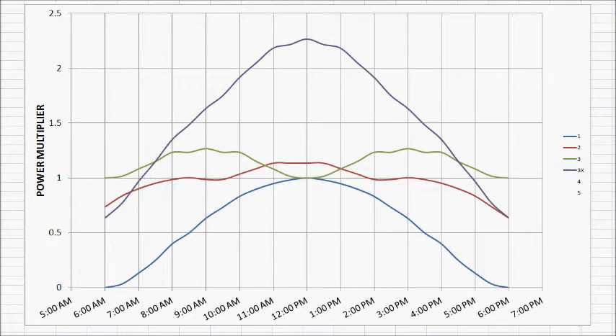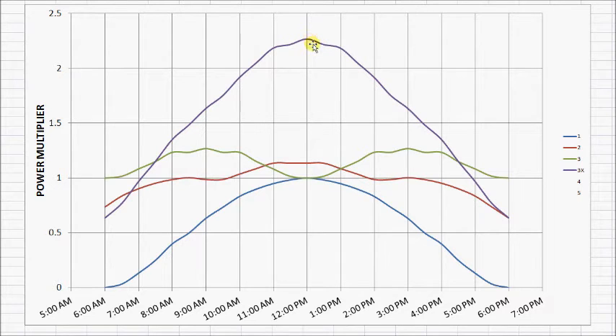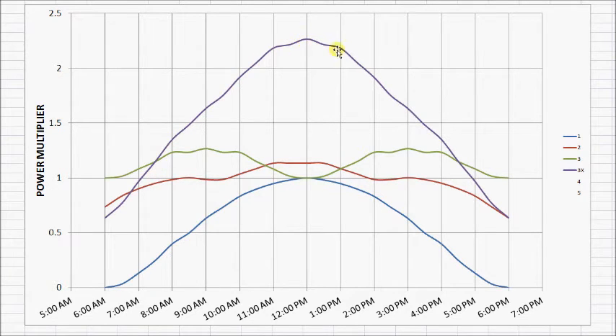If we look at the other configuration of three panels — one to the southeast, one to the south, and one to the southwest — clearly all three of them are contributing very well. The one facing due south is putting in its full amount, and the ones facing southeast and southwest are doing about two-thirds of their production right at noon. So you'll see that is a very strong peak at noontime, but less than even the two-panel configuration in the early morning and in the evening.